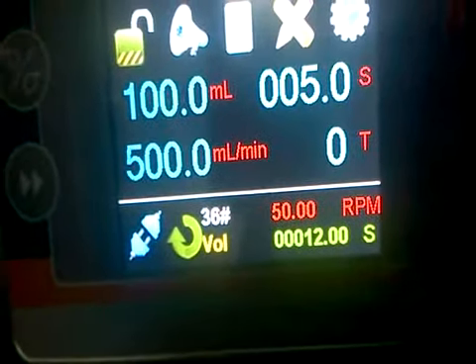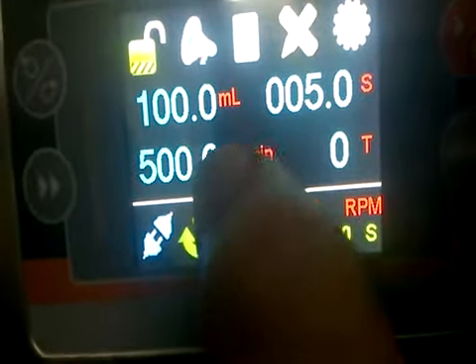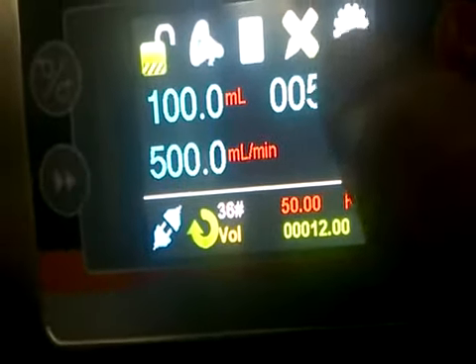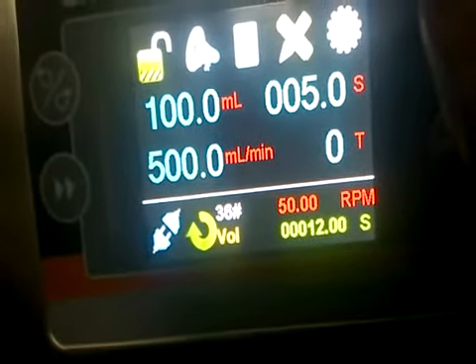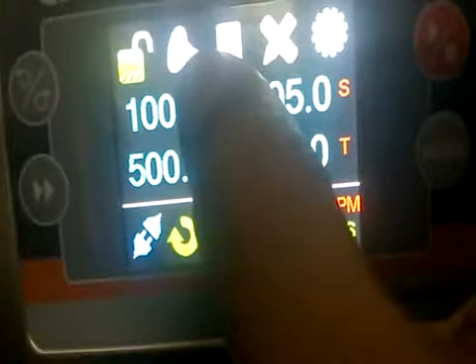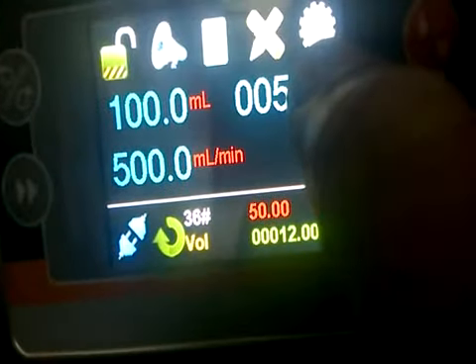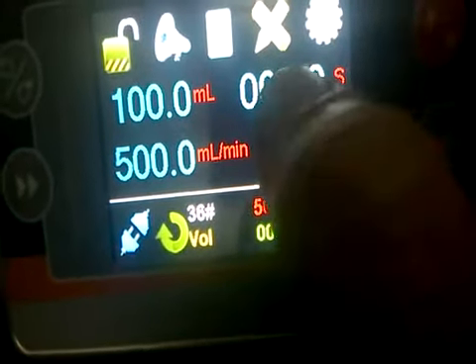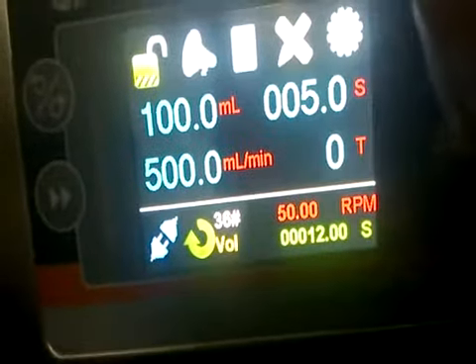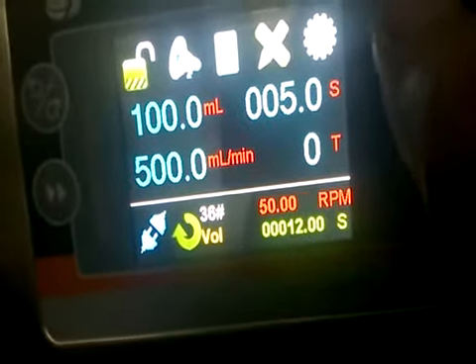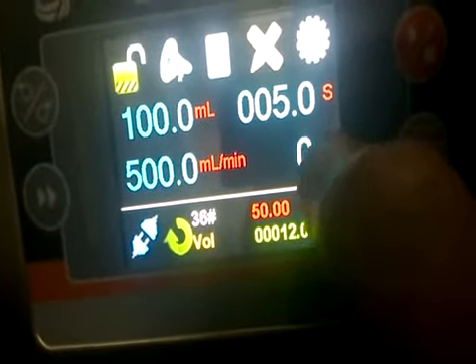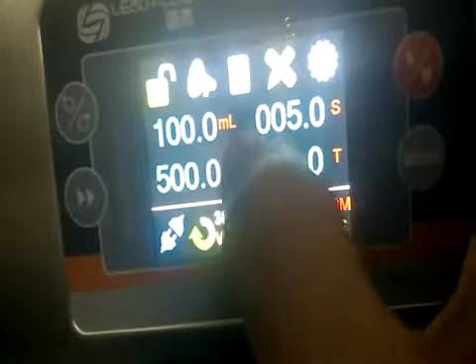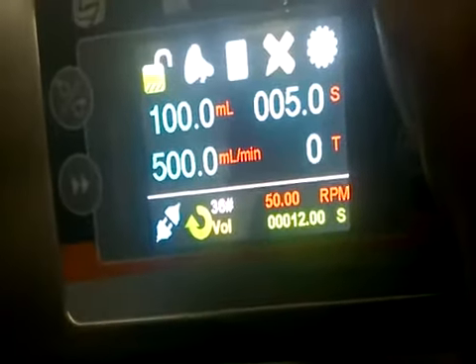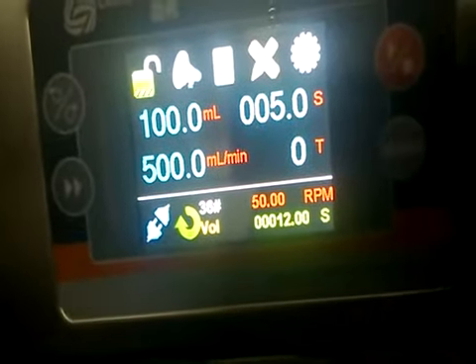Now the next mode is volume mode. This is interesting. In the volume mode, we can set the flow and we can set the volumes and we can set the time interval, and this machine will run for this volume 100 ml, then it will wait for 5.0 seconds, and then again it will run for 100 ml, and then again it will wait for 5 seconds. For that, the T has to be kept at 0. Suppose I have given 500 ml per minute. With a flow of 500 ml per minute, 100 ml volume is set and 5.0 is the gap. Let us see how it does.